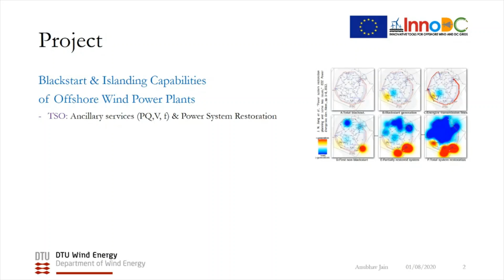Presently, wind turbines are exempt from frequency stability and restoration services, but inertia emulation for fast frequency response and power oscillation damping, along with local voltage control for controlled islanded operation, are expected in the upcoming grid codes. As far as power system restoration is concerned, although the grid code does already include black start and islanding capabilities as options for wind power plants where TSOs can request these functions, the active participation of wind power plants early on in the system restoration right now is very limited.